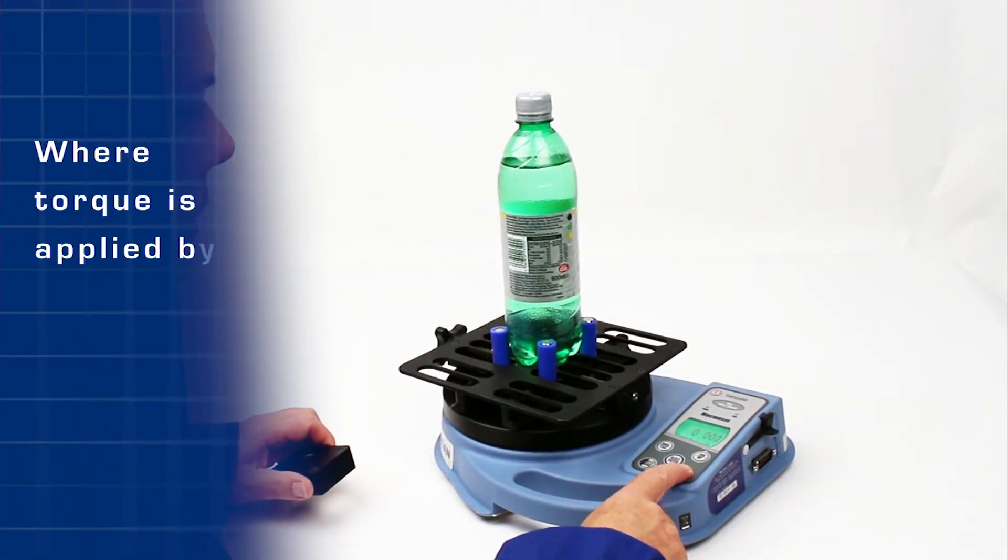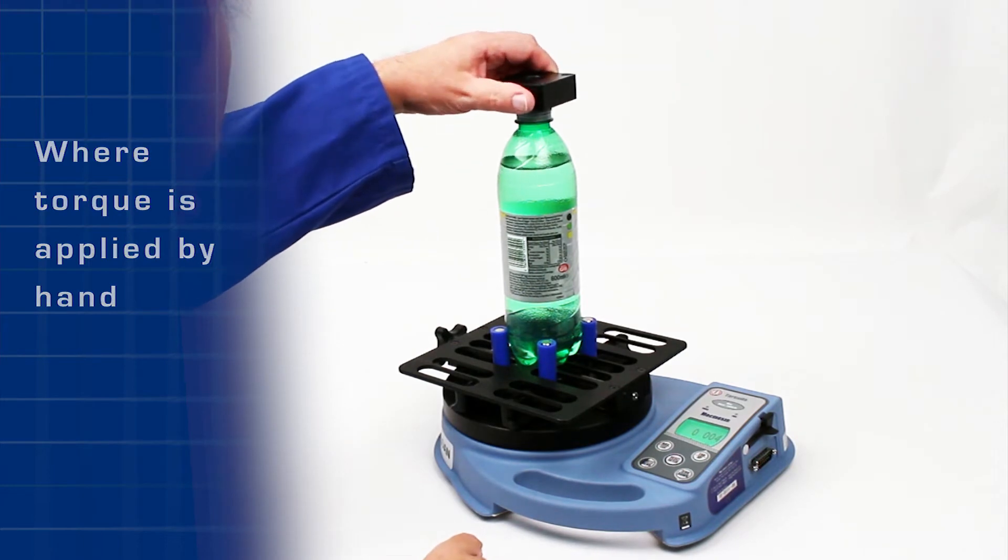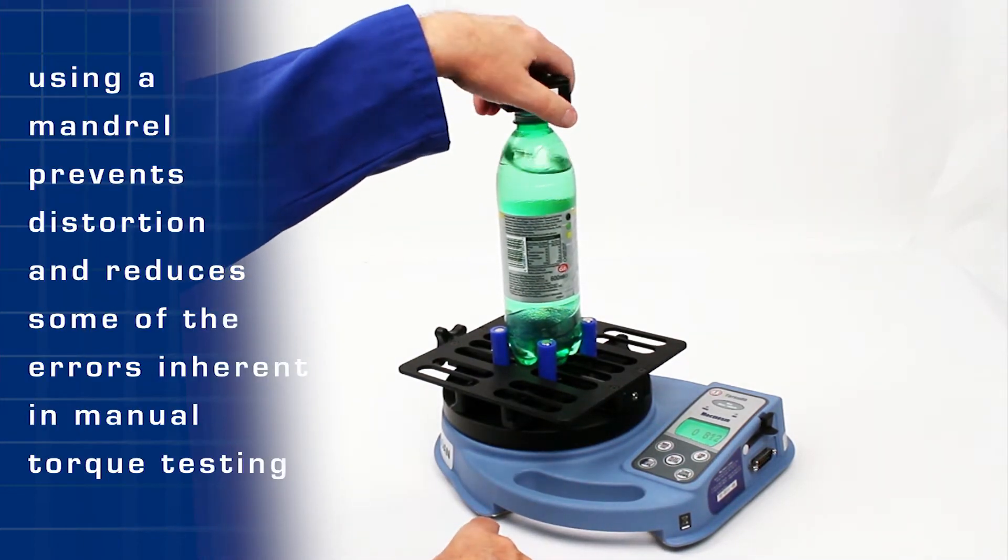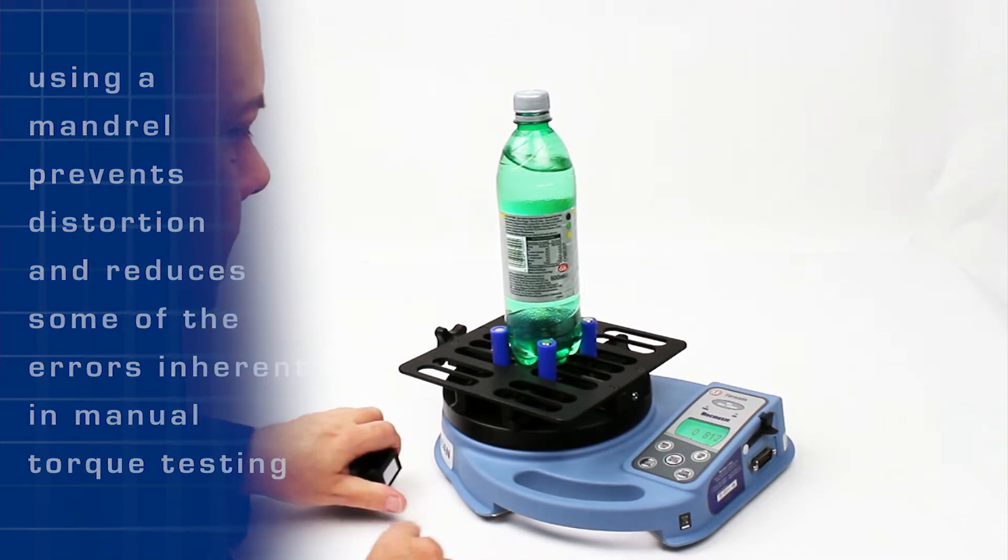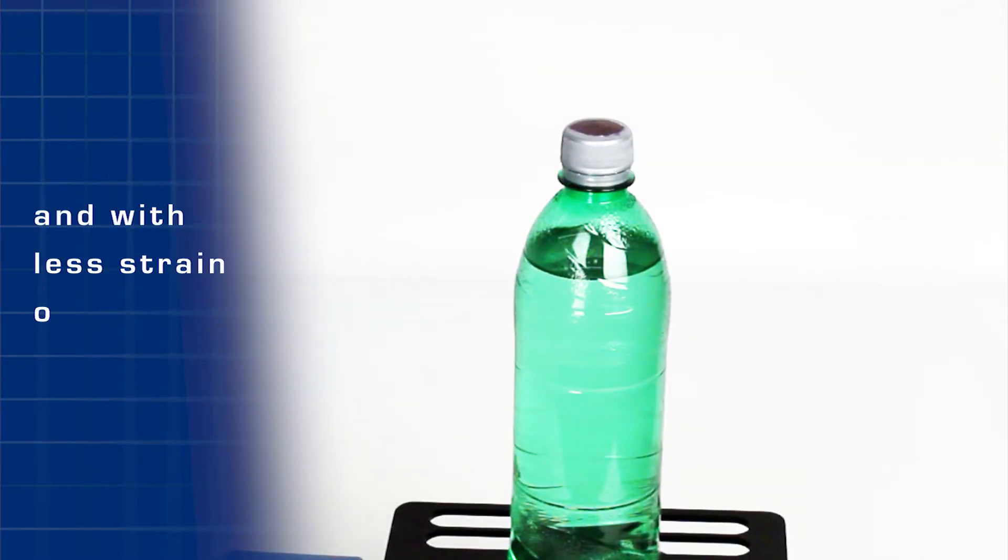But where torque must be applied by hand, using a mandrel still prevents distortion and can reduce some of the errors inherent in manual torque testing, and with less strain on the operator.